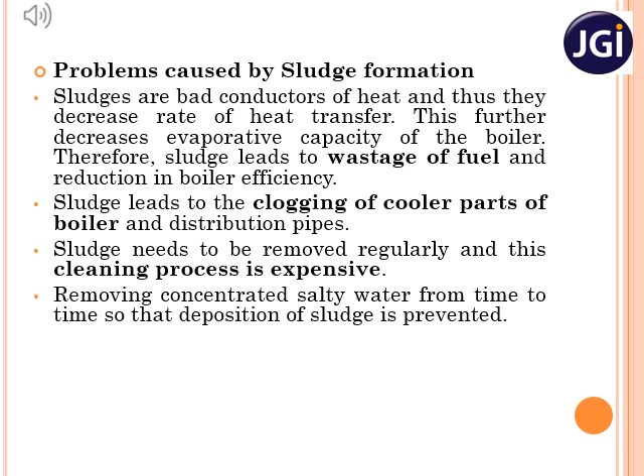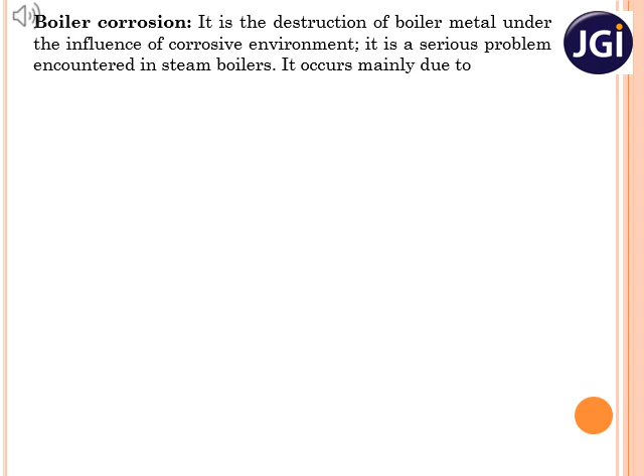Students, the first problem was scale and sludge formation. The next problem that can be expected due to impure water is boiler corrosion. The destruction of boiler metal under corrosive atmosphere is called boiler corrosion. This occurs mainly due to the presence of dissolved oxygen, carbon dioxide, and magnesium chloride. The dissolved oxygen present in the boiler feed water can attack on the boiler metal under high temperature and pressure, which will be there inside the boiler. Refer the reactions given here. This attack leads to the formation of rust.